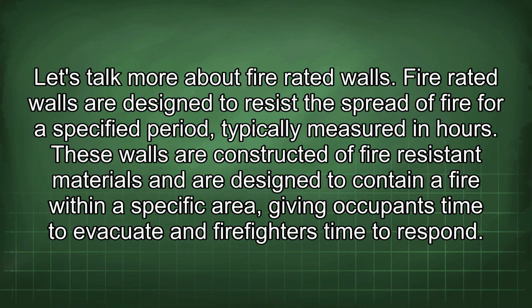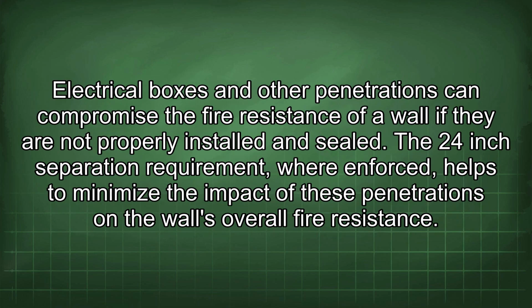Let's talk more about fire-rated walls. Fire-rated walls are designed to resist the spread of fire for a specified period, typically measured in hours. These walls are constructed of fire-resistant materials and are designed to contain a fire within a specific area, giving occupants time to evacuate and firefighters time to respond. Electrical boxes and other penetrations can compromise the fire resistance of a wall if they are not properly installed and sealed. The 24-inch separation requirement, where enforced, helps to minimize the impact of these penetrations on the wall's overall fire resistance.